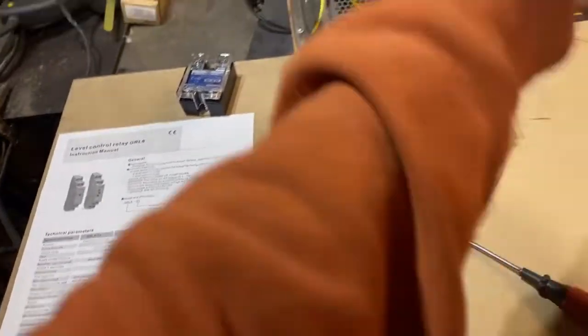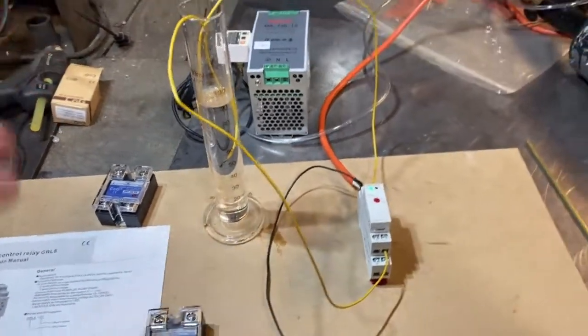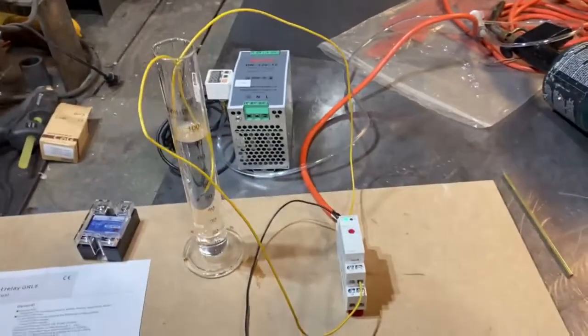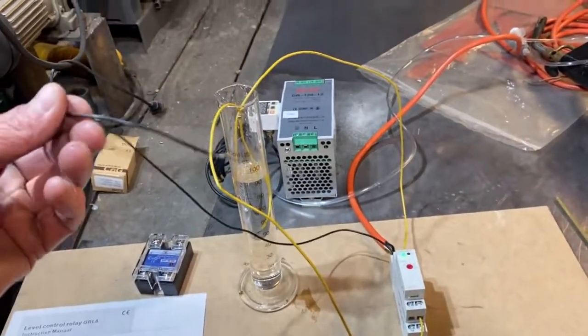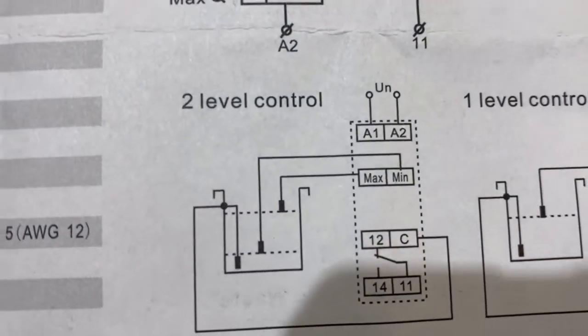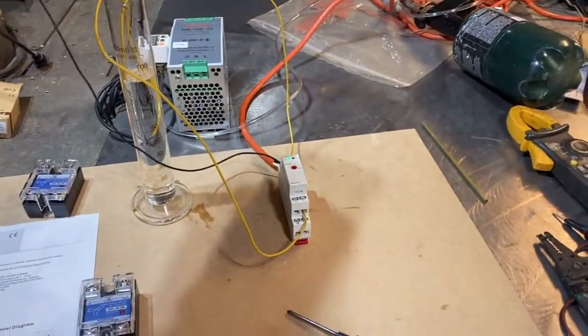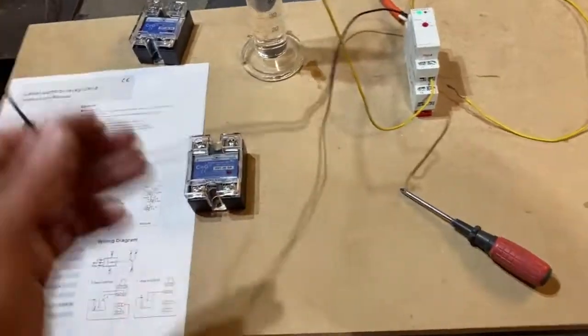So now when fluid goes back into the tank and it hits the bottom probe, nothing happens. That's what we want. And when the tank is filled back up, the level eventually hits the upper probe that's connected to max there on two level control, and the relay fires.